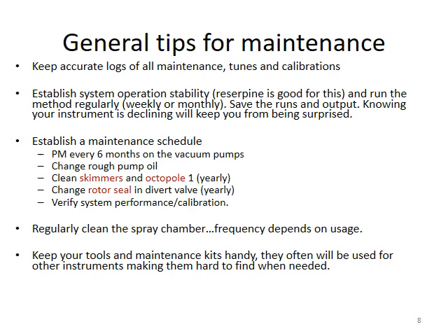I believe there is another good practice. You can have a well-set method, which can be used to monitor the overall performance of the QTOF. In this well-set method, you should have the mobile phase well indicated. What is the column? What is the gradient? What is the acquisition mode? Is it MS, or just MS1?